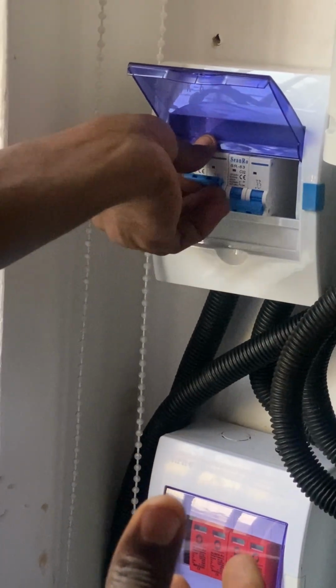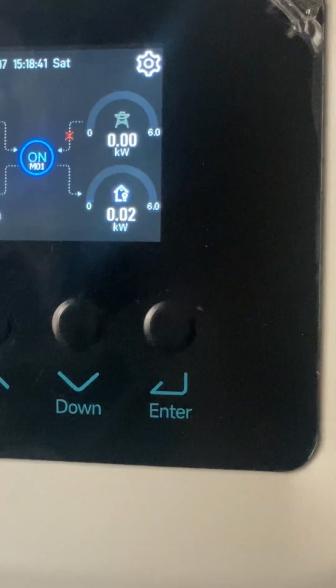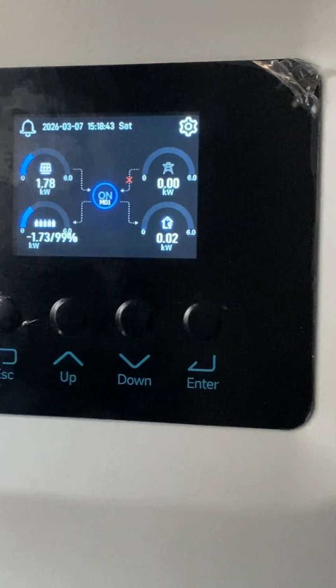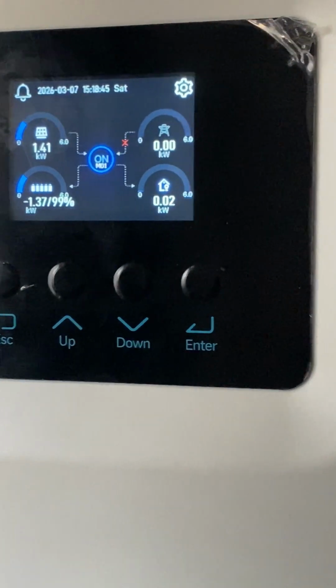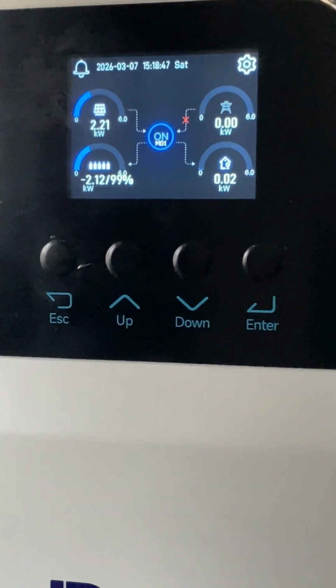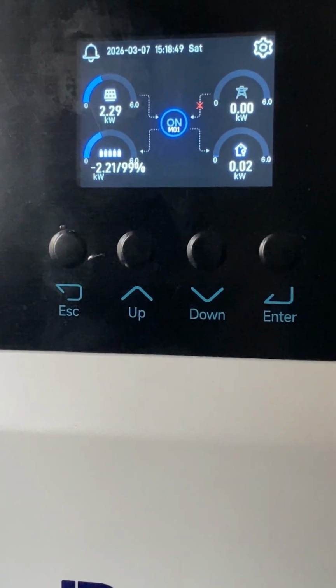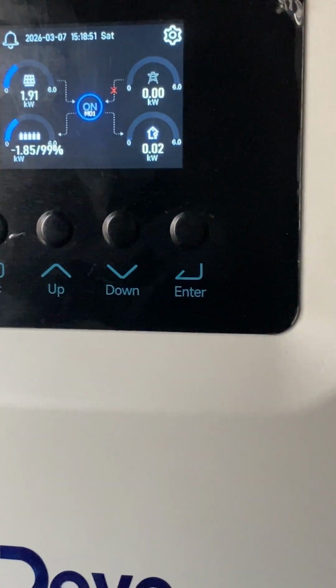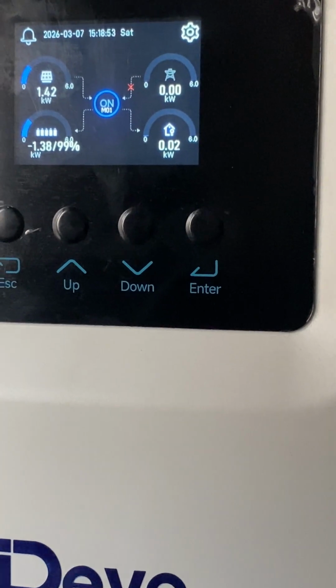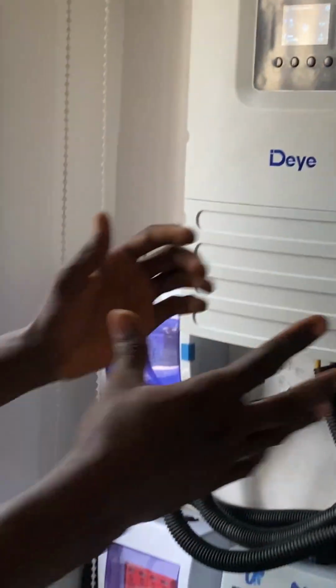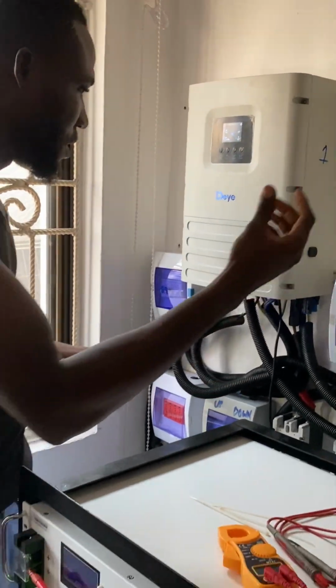So this is our input breaker, which we are powering up now. It will take the inverter 60 seconds to bring it up. The reason might be that your NEPA supply is fluctuating, or the generator is not good, so the inverter needs to check the voltage and the frequency of the source trying to charge it.